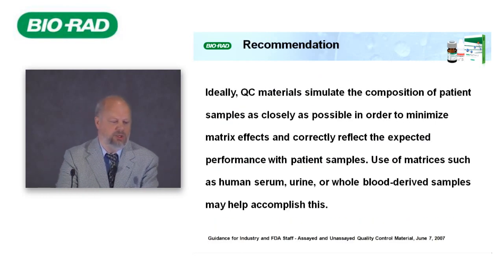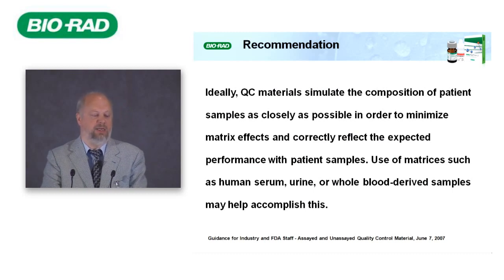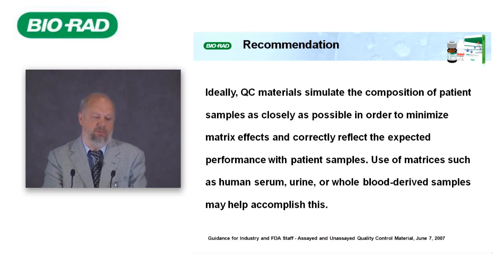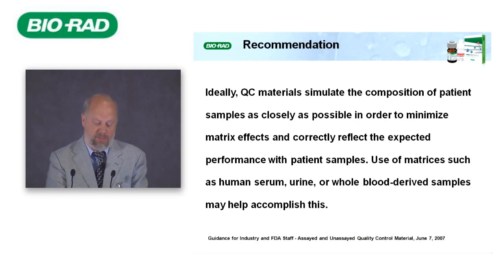The recommendation of IFCC is that ideally QC material should simulate the composition of patient samples as closely as possible, to minimize matrix effects and correctly reflect the expected performance on patient samples. Use of matrices such as human serum, urine, or whole blood-derived samples may accomplish this.